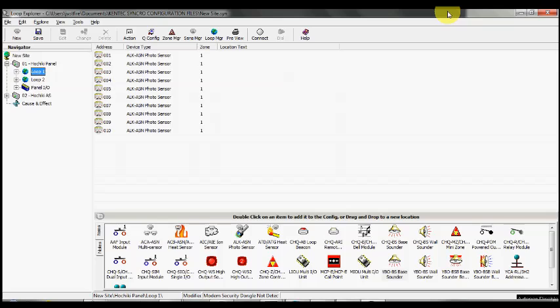This would then start the second timer, which is the investigation delay, and that could be maybe three to four minutes to allow someone to go across the actual site to find the activated device and to determine what the cause actually is. Obviously, if a second smoke detector was to go into fire or indeed a call point is activated, then the system goes into full evacuation.